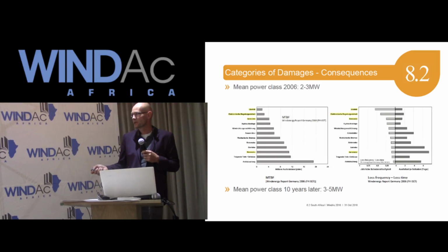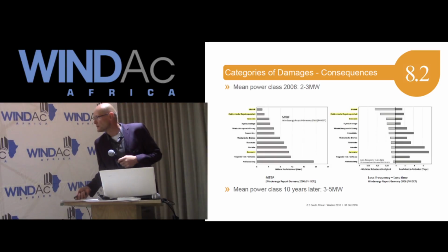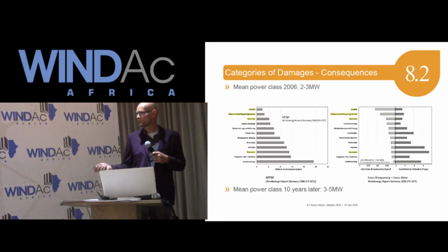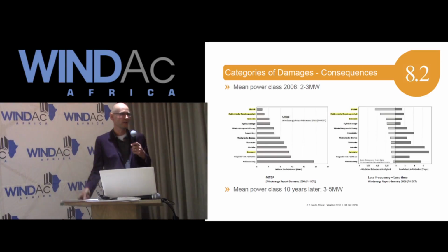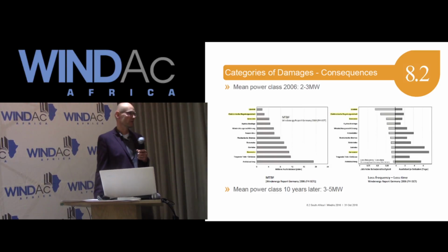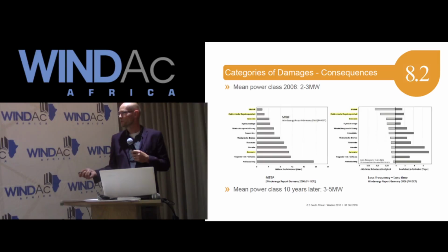In this range, the mechanical parts last somewhat longer, but on the other hand, the downtimes following these failures are shown here on the right side. For electrical parts, it's very short, just a few days, 1 to 2 days maximum to replace switches or such components. Whereas the mechanical parts, like gearboxes, hydraulic systems, pumps, and so on, take more time to replace or repair, which means a longer standstill time.